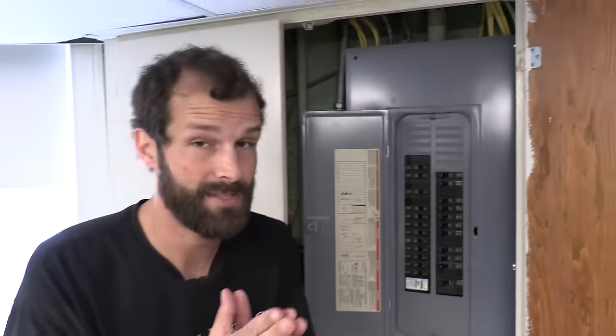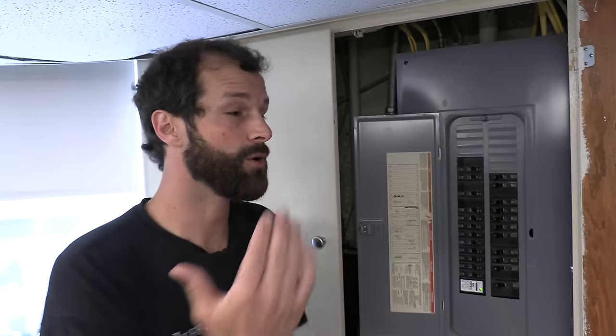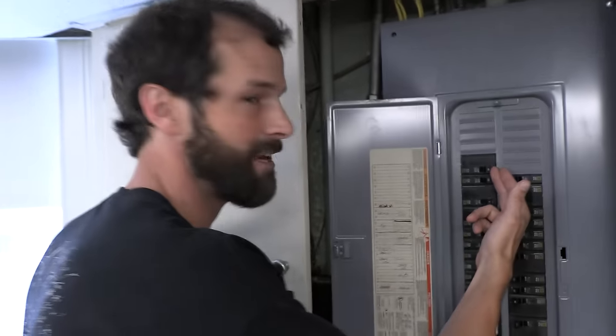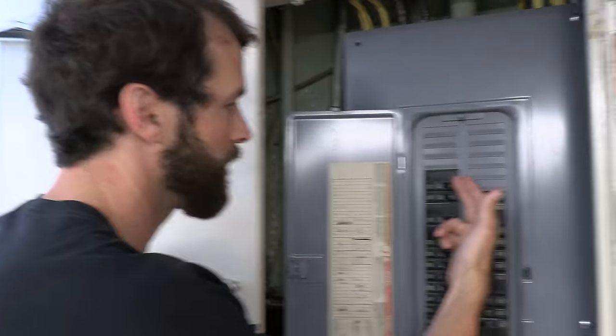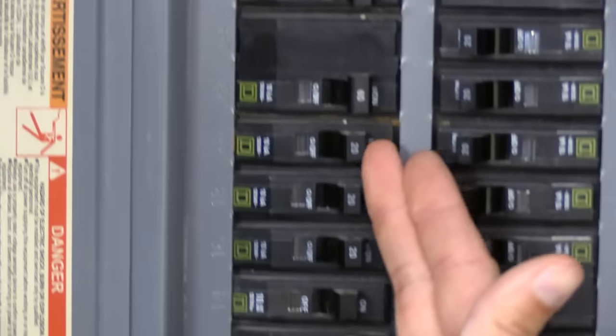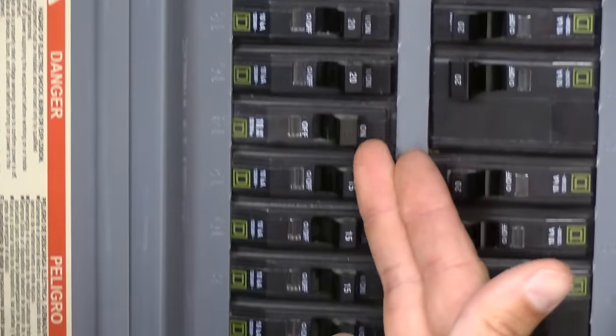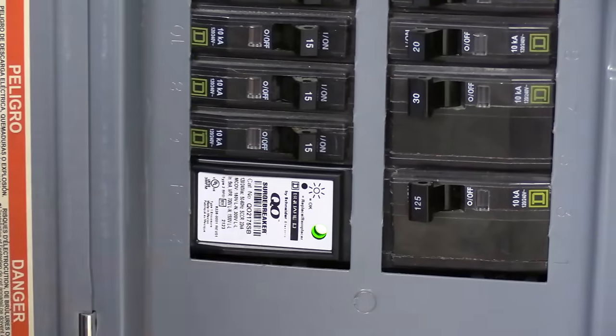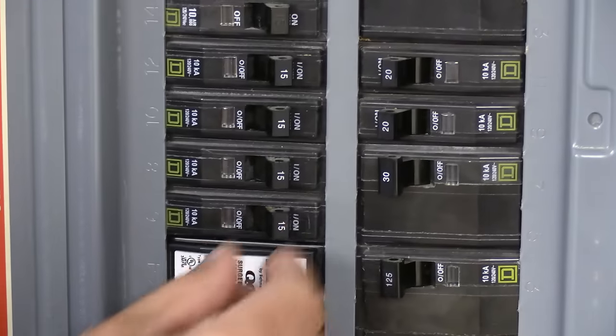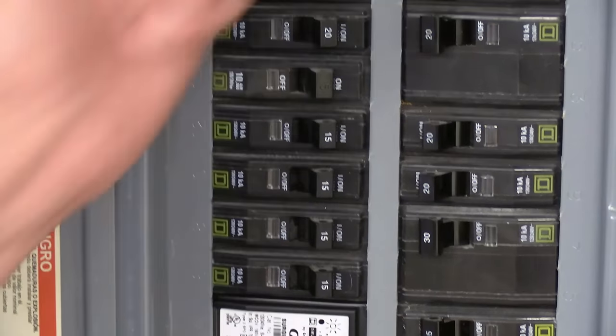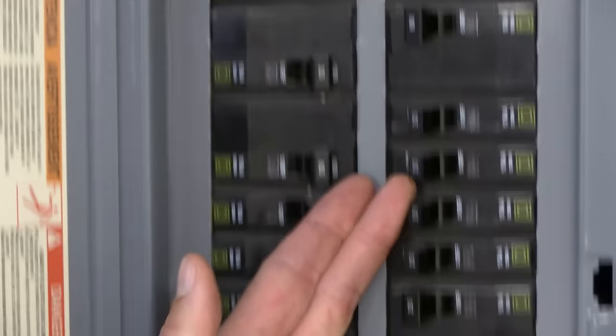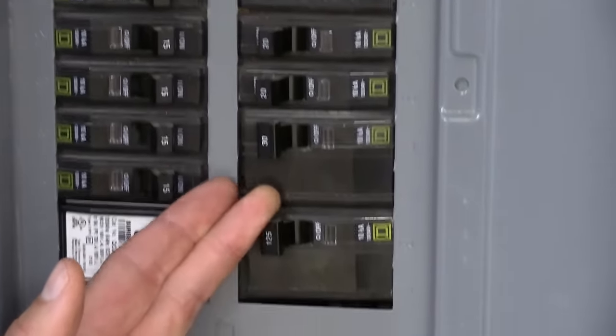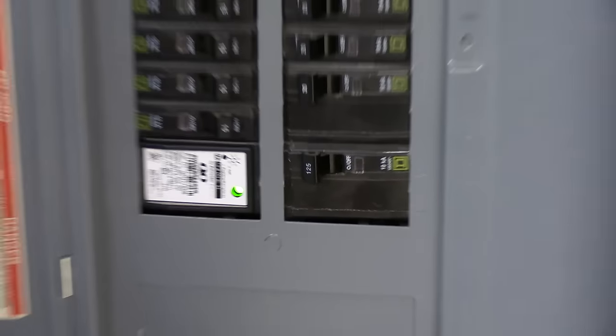Now here's one thing that happens. Occasionally breakers trip and they don't go to the trip position. So when I'm investigating a panel for a power outage, what I do is I run my finger lightly down the inside. Light pressure. And sometimes you'll encounter a breaker that then pops over to that trip position we just talked about. And you can turn it off, check for cause of fault, and reset it. Now a breaker that is in the tripped position is off. It's no longer energizing the circuit.